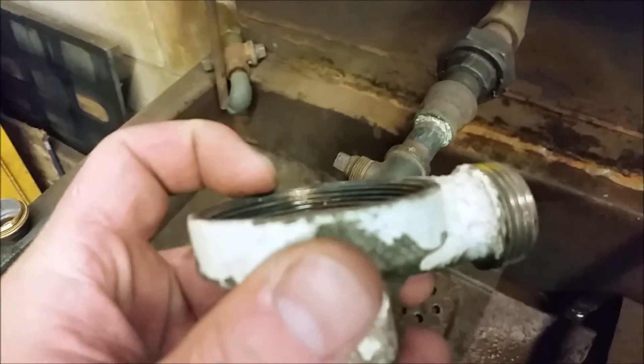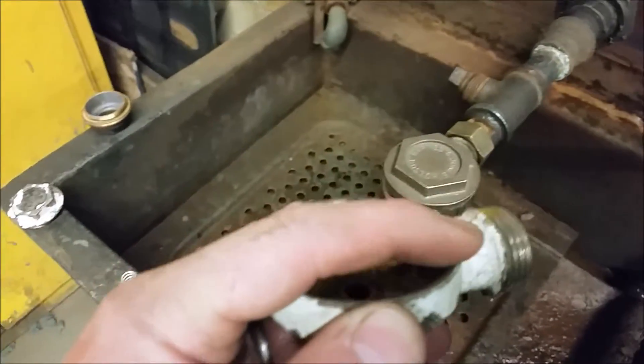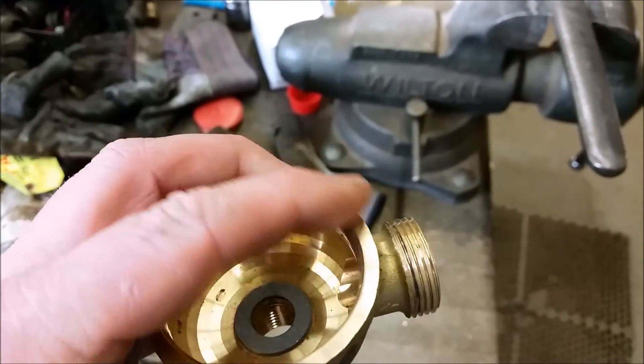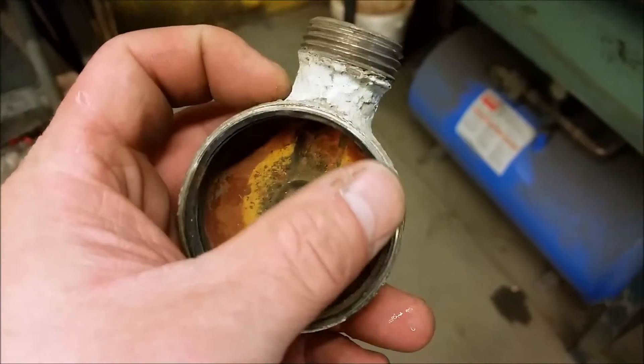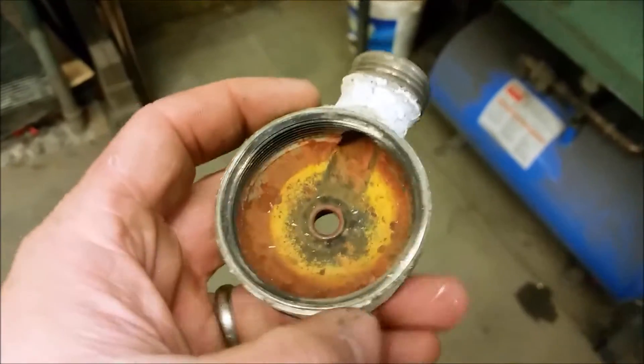The problem with these Dunhams is the actual mating surface comes to a point, which is much different than a normal trap like this, which has a nice flat wide machined-flush surface. That's where we get a really good sealing surface because all of our covers are machine flat too, so that requires no gasket. Whereas this is not a very wide sealing surface — it comes to a point — so a lot of times we do end up putting a gasket on that.